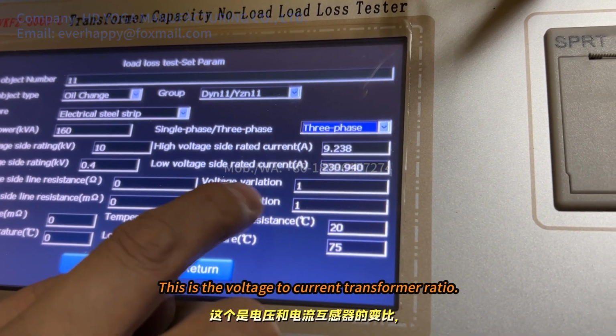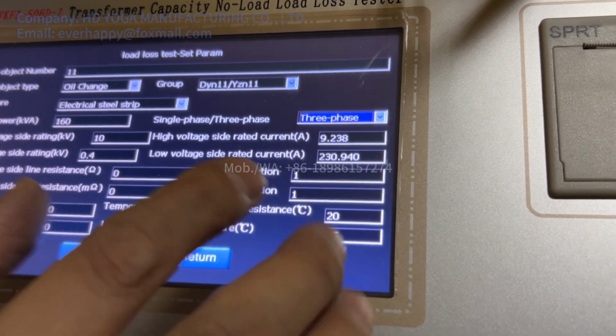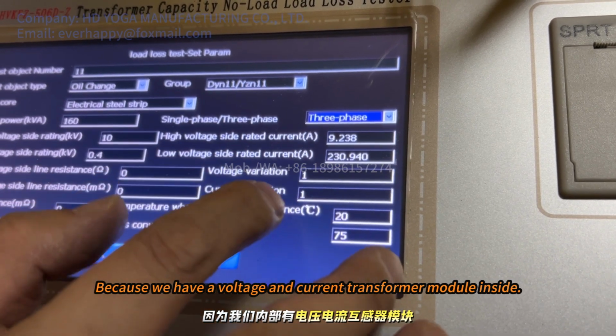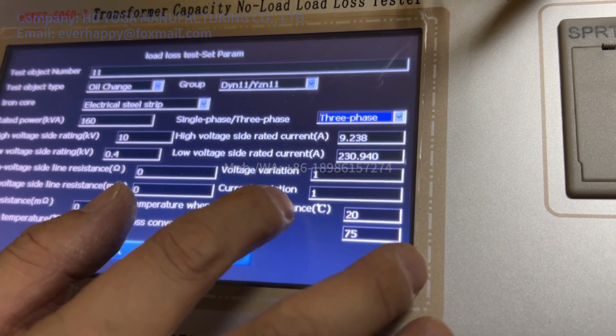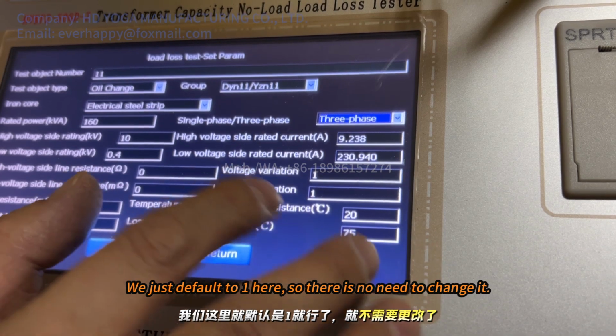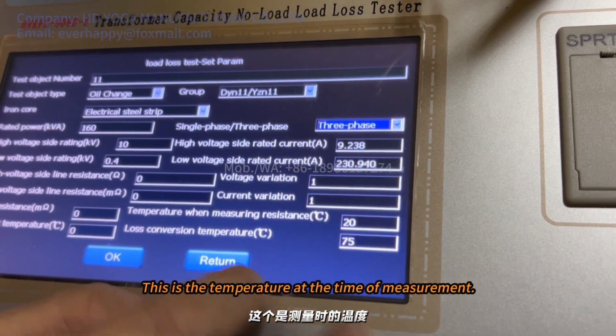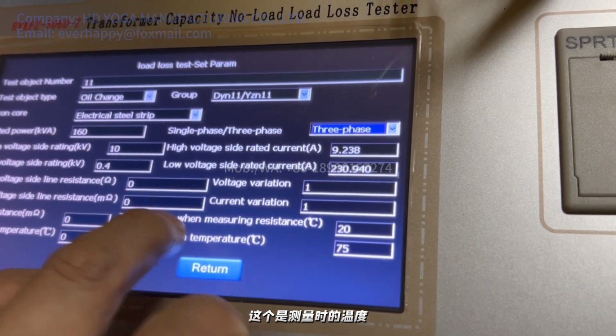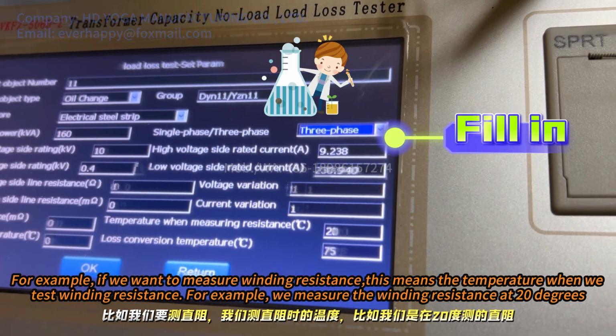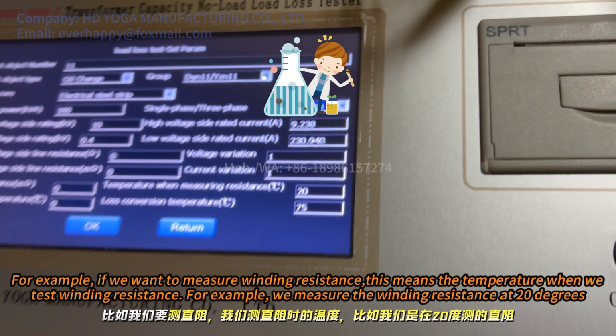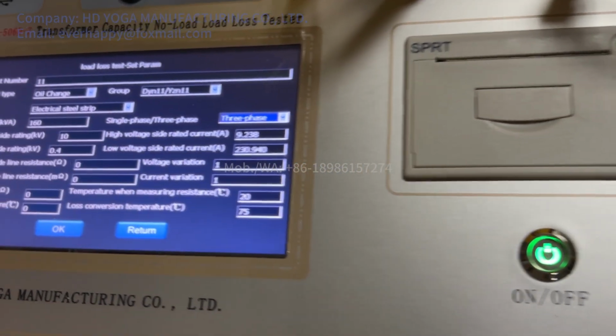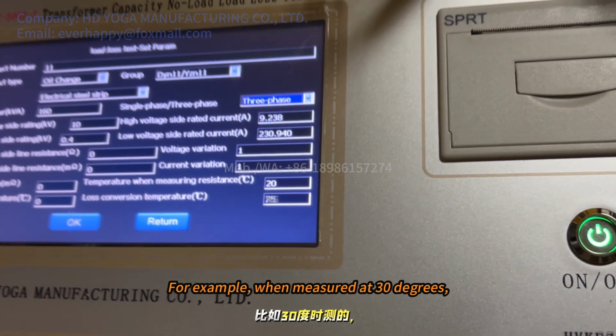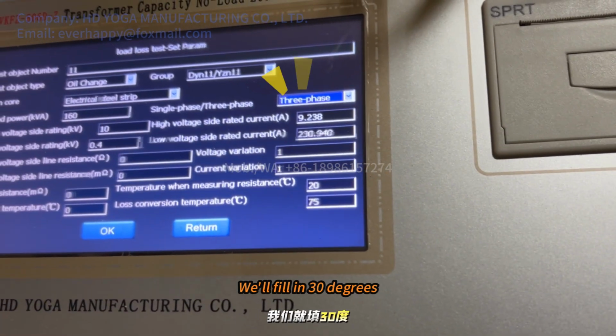This is the voltage to current transformer ratio. Because we have a voltage and current transformer module inside, we just default to 1 here, so there is no need to change it. This is the temperature at the time of measurement. For example, if we want to measure winding resistance, this means the temperature when we test winding resistance. For example, we measure the winding resistance at 20 degrees, we'll fill in 20 degrees. When measured at 30 degrees, we'll fill in 30 degrees.